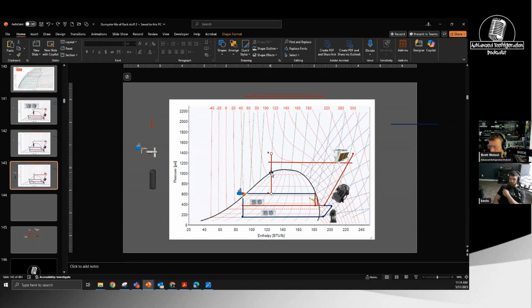So when I lowered it from 25 to 15, I dropped the drop leg temp to like 12, 13 degrees when it was running like 90. So it was running like that because we were flooding out the heat exchangers basically. That's going to bring you all the way over to, it's going to be really outside the dome.